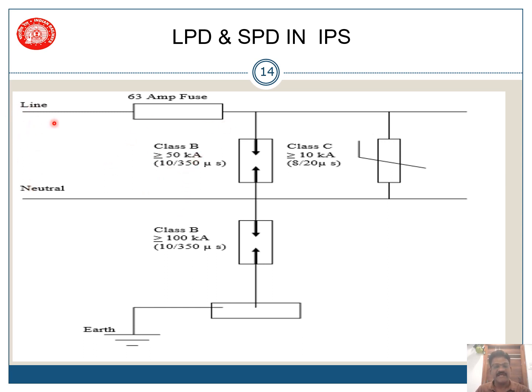So when supply is coming, line and neutral, we have a 63 amp fuse. From there, the supply is going to IPS. Neutral is also going to IPS. But in the middle, we have one class B which has a protection level of greater than 50 kiloamps, 10 by 350 microseconds waveform, while one at greater than 100 kiloamps is provided between neutral and earth with the same waveform. While the waveform will be reduced for class C, it is 8 by 20 microseconds with a protection level of greater than 10 kA.